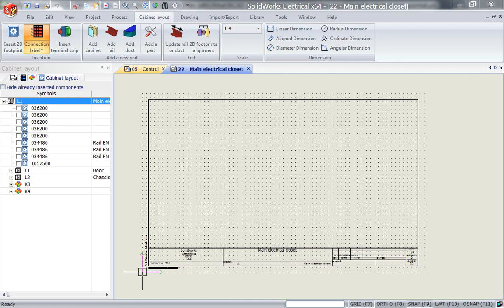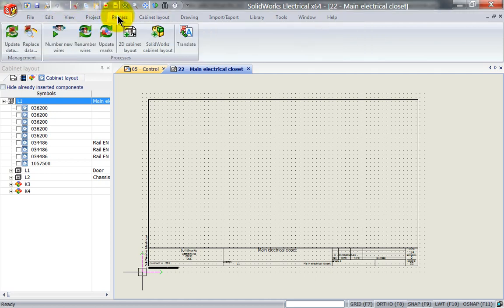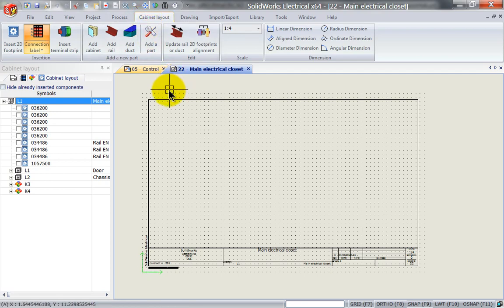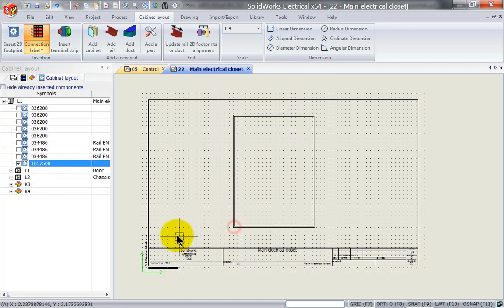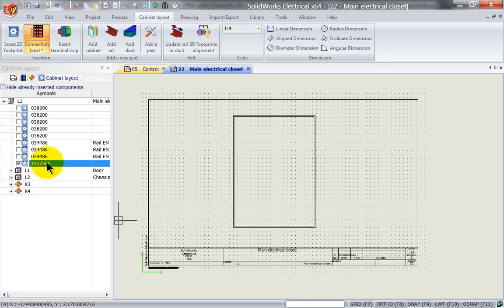If you decide to go the 2D way inside SOLIDWORKS Electrical and create a 2D cabinet layout, you can simply go to the Process tab on the ribbon and left click on 2D Cabinet Layout. This will bring you to the cabinet layout screen, and as you can see on the left-hand side I've got my ducts and rails already added to the project. I've also added a cabinet here, and I can right-click and say Insert as Cabinet to place it on the drawing. It's quite a simplistic representation because if SOLIDWORKS Electrical doesn't have a DWG or 2D footprint assigned to the manufacturer's data, it will just use a generic symbol with the width and height specified in the manufacturer's data.